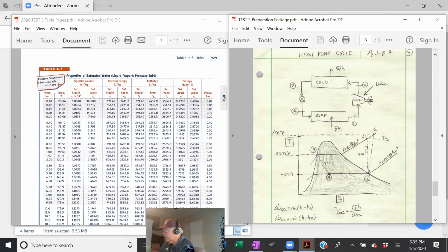So going into the compressor, we have to come out at least here and maybe even a little further, because compressors will not compress liquid. If you come out of here with a liquid and try to compress it with a compressor, it's going to tear the compressor all to pieces. What we're doing with the compressor is getting up to higher pressure. And in the case of refrigerants, just as in the case of air compressors, when we go up in pressure, we get higher in temperature. In this case, that's what we want. We want a higher temperature, and we live with a higher pressure. I'll explain why in a minute.